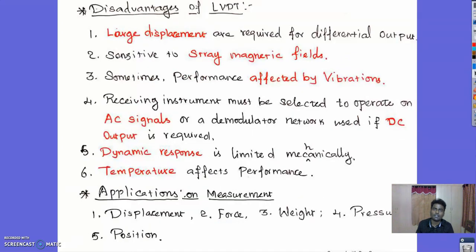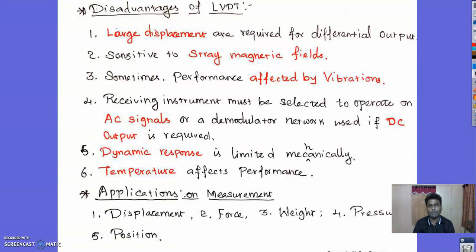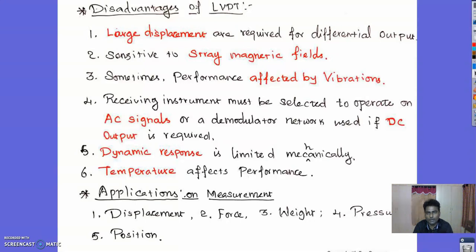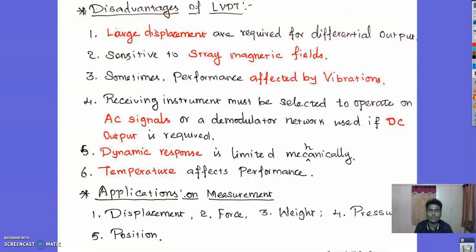The disadvantages of LVDT are: it requires large displacement for a differential output; it is very sensitive to stray magnetic fields; performance may be affected by vibrations; the receiving instrument must operate on AC signal, or a demodulator network must be used if DC output is required — meaning if the output device is a DC device, the AC signal must be converted to DC; dynamic response is limited mechanically; and temperature affects the performance of the LVDT.